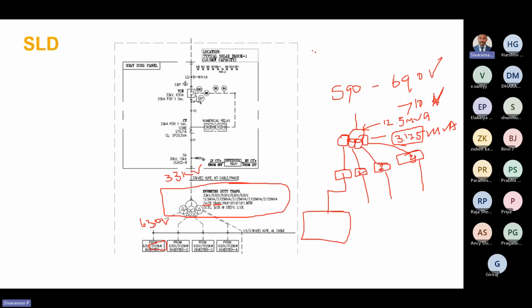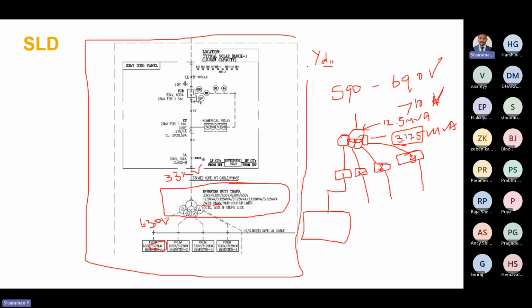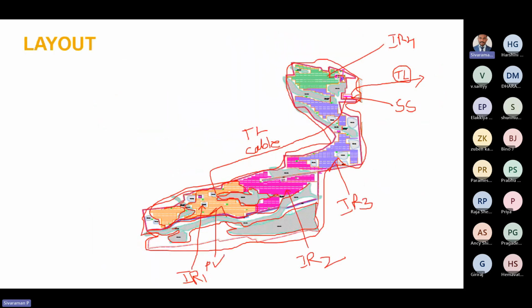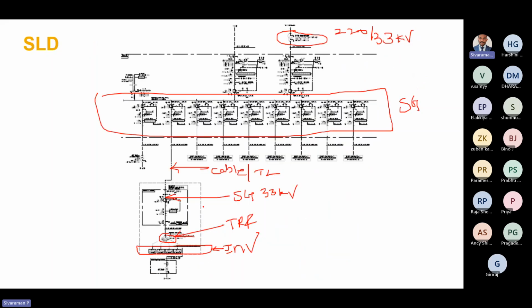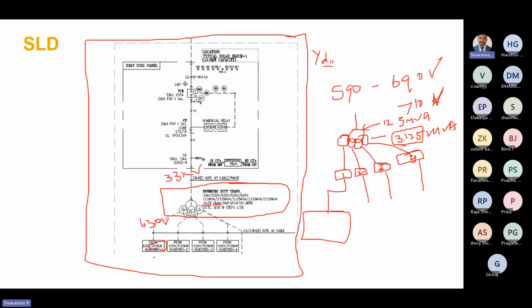So the vector group is there. On the high voltage side, it is star. On the low voltage side, it is delta. D11, D11, D11, D11. It's not having the OLTC. It will have the OCTC, off circuit tap changer. Okay, then here the medium voltage cable will come, connecting the transformer to this inverter room switch gear. So this entire part will be in one inverter room. In this layout I mentioned here, inverter room one, in that room these inverters, inverter duty transformer and switch gears will be placed.